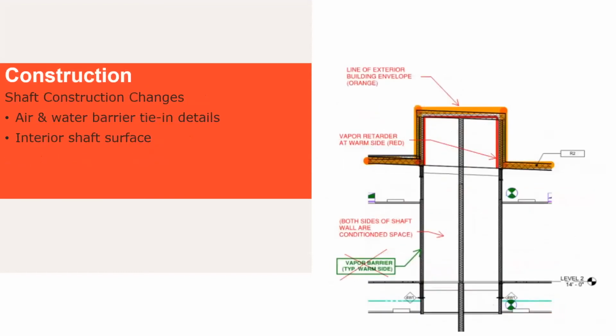The problem we still ran into was - we probably should have painted the inside of that shaft instead of just using DensGlass. Now you have an accessibility issue in that shaft - integrating a D-ring or something to get in and fix something if it got in there, say a bird somehow got in. Accessibility in these shafts should be a consideration, whether it's a D-ring, a place to tie off to, or a removable damper assembly so you can access it from below and leave a rope in there - some way to access and inspect is a good idea.